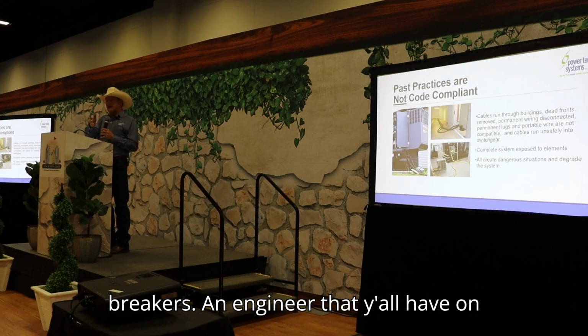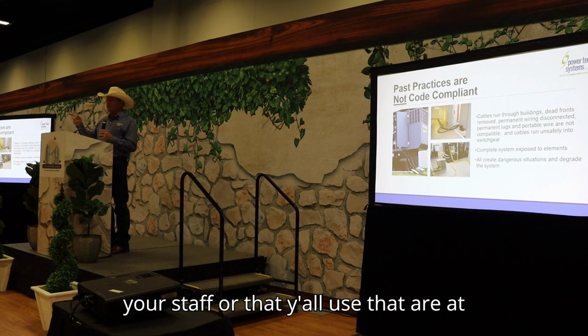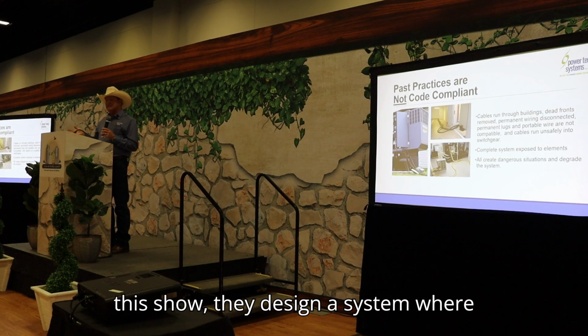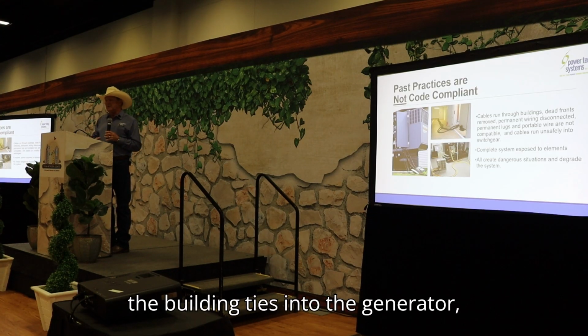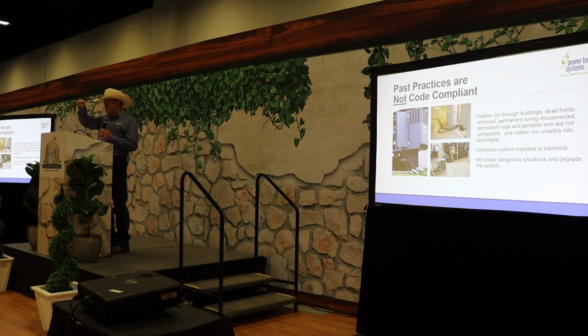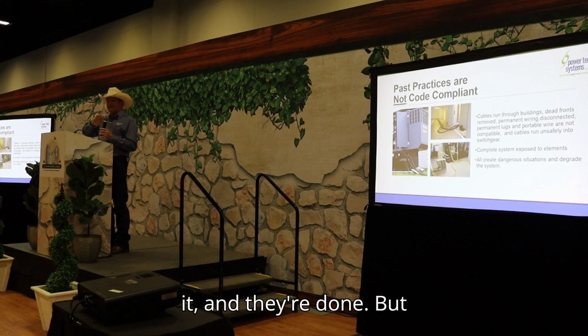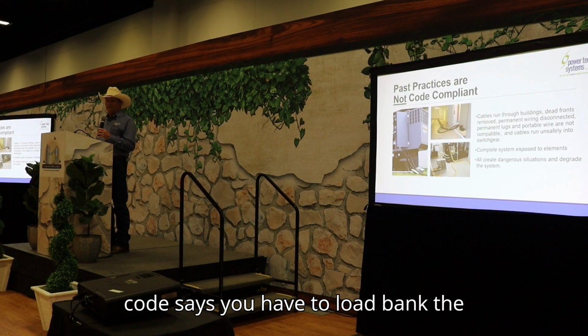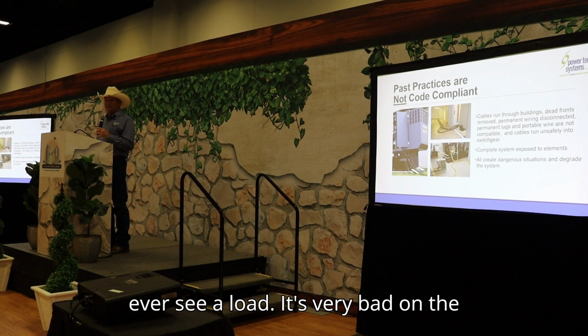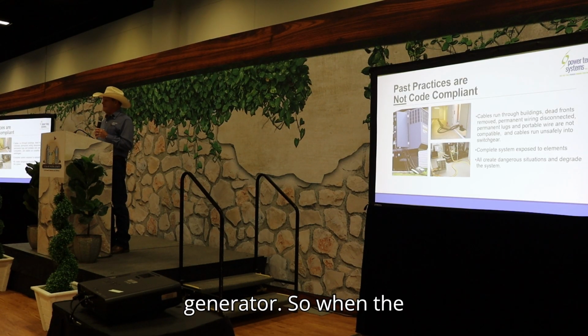An engineer that y'all have on your staff, or that y'all use, that's at this show - they design a system where the building ties into the generator, they torque everything down, they mark it, and they're done. But code says you have to load bank the generator because they typically don't ever see a load. It's very bad on the generator.